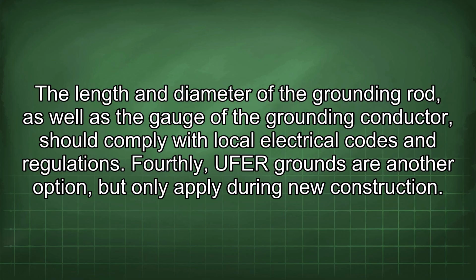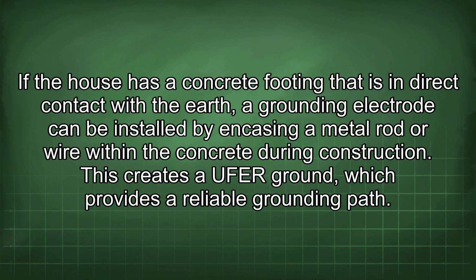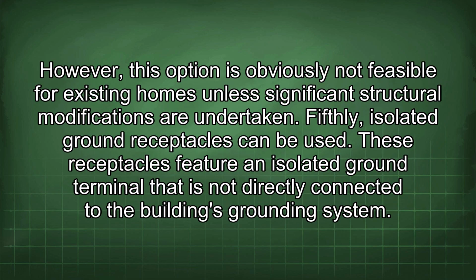Fourthly, UFER grounds are another option, but only apply during new construction. If the house has a concrete footing that is in direct contact with the earth, a grounding electrode can be installed by encasing a metal rod or wire within the concrete during construction. This creates a UFER ground, which provides a reliable grounding path. However, this option is obviously not feasible for existing homes unless significant structural modifications are undertaken.